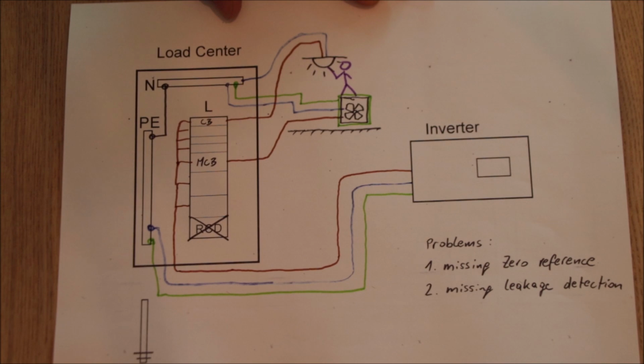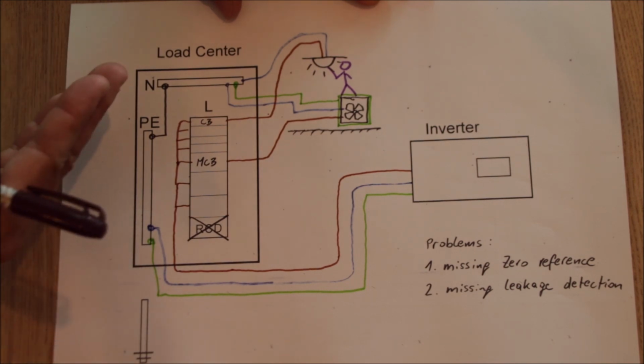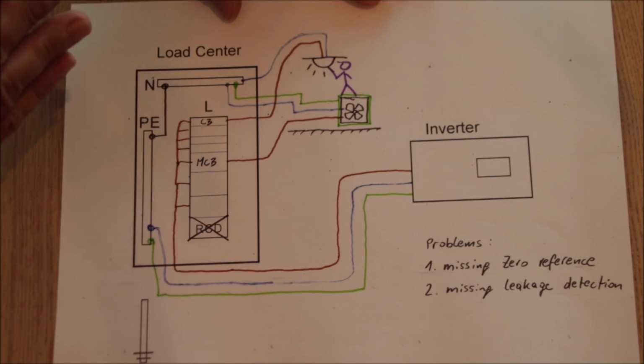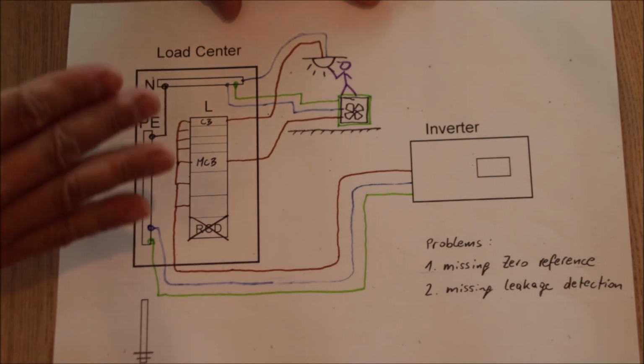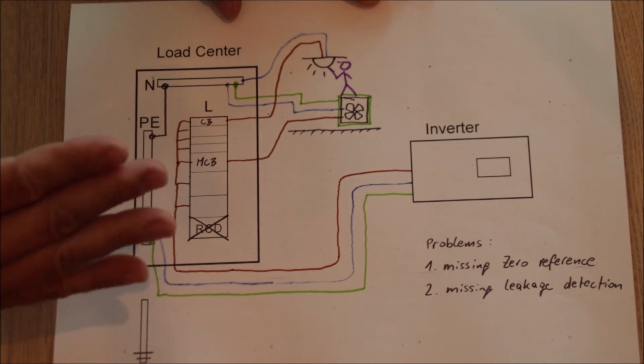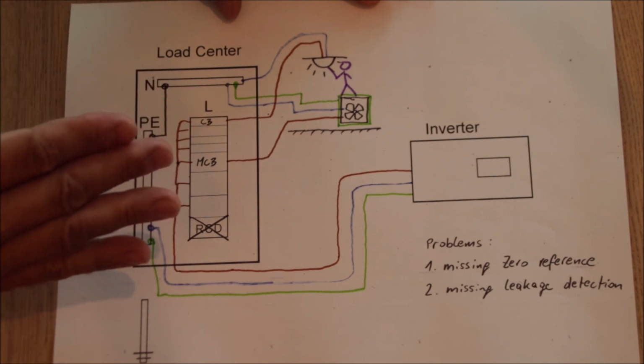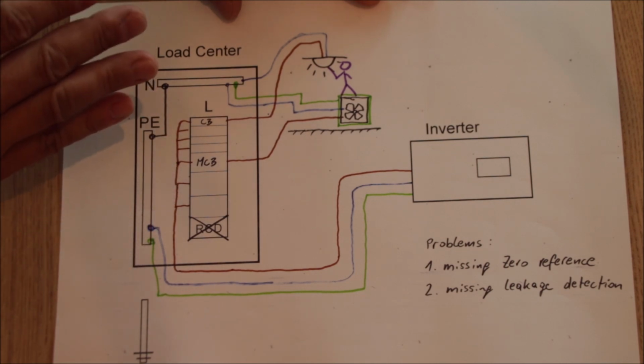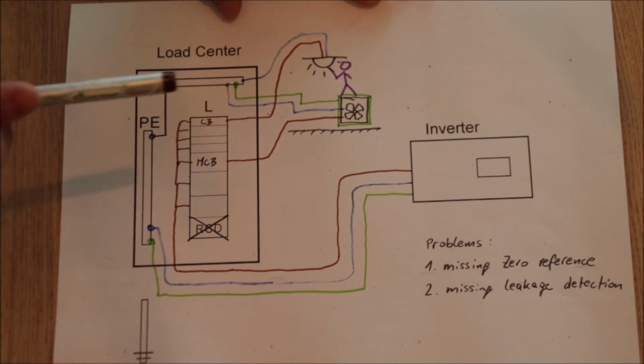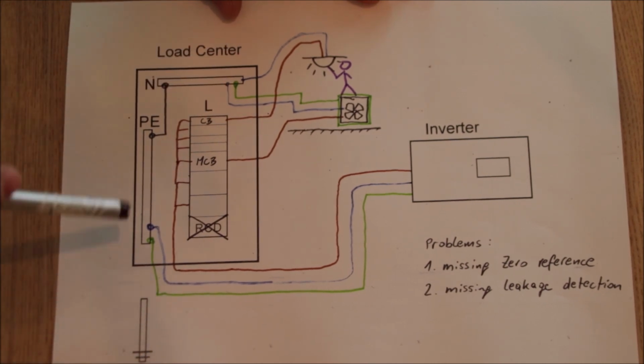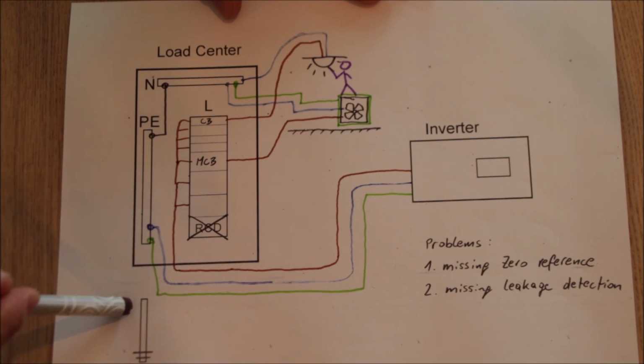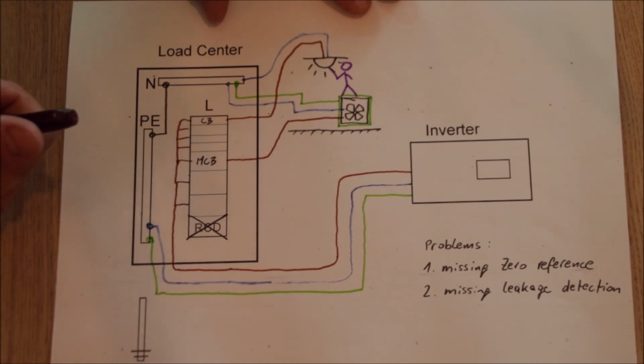And then, what is very important, he says that what he did, because his system is a pure off-grid system, his all-in-one inverters are not connected to the grid. You know, the AC in is not used. So there is no need for grounding. So he did not connect any of this to a source of ground, right? So no grounding rod, or no using of the house internal grounding system, which you also could do. First, no grounding, no PE to the system at all.